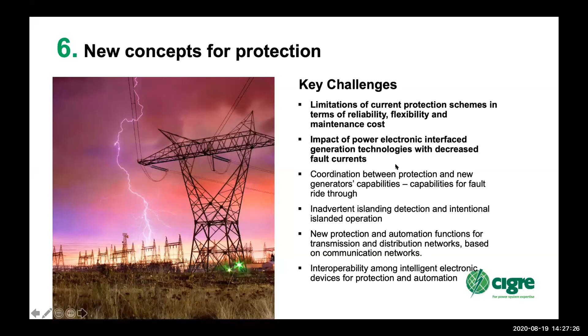The impact of power electronic interface generation, with decreased fault currents and increased fault currents, increased voltages, and multi-earth systems, now makes it very difficult for the protection we used to have with power going in one direction to actually operate. This is really one of the challenges we have.